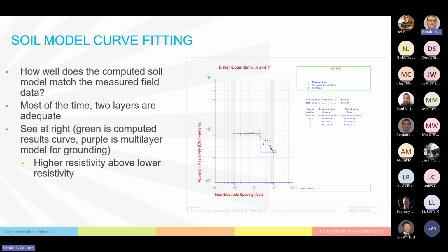Now, fitting that curve. How well does the computed soil model match the measured soil data? Most of the time you're going to find that 2 layers are adequate. And here I show a screenshot of CDEGS results where 2 layers really are adequate. Walking through what we see here, these blue dots are individual readings. They're reasonably close to one another throughout. We've got this green curve, which is the model that CDEGS computes of the soil overall. And then we've got this purple, staircase curve, which is the model that CDEGS recommends to use in your grounding design. You can also see the RMS error here is 10.84%, very low. This is a great soil model.